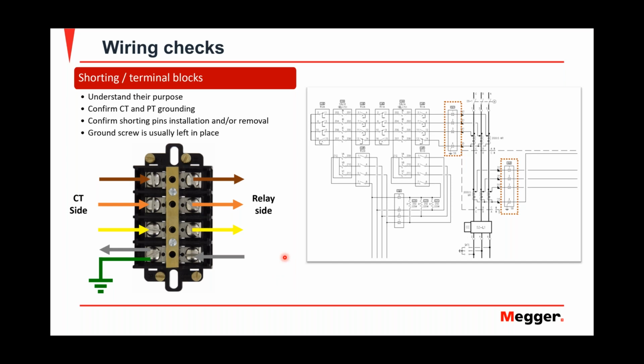Understand the purpose of a shorting block. Know the grounding, where the location of the grounding is. So this is your shorting block right here. Usually I've seen CTs either grounded at the shorting block or at the CTs themselves, but it's usually on the CT side, not at the relay side. Confirm the installation and the removal of the shorting pins. If you've never seen a shorting block, this is how it looks. Your currents from the CT come in. This is your return, and then they go to the relay, and then you short out the currents. If you want to isolate the relay or your meter, you use these 4 screws to short them out via this bar right here.